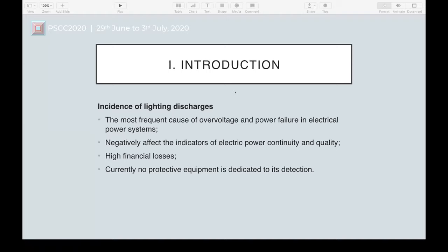This study deals with the incidence of lightning discharges in electrical power systems. It is the most frequent cause of overvoltage and power failure, which can damage equipment and interrupt power supply. As a result, it can negatively affect indicators of electrical power continuity and quality and cause high financial losses. Currently, no protective equipment is dedicated to dealing with lightning discharge detection. Power utilities struggle to provide explanations to regulatory agencies regarding interruptions from this natural phenomenon. The method proposed is not intended to be used as protection against lightning discharge, but rather as a post-operation diagnostic tool.